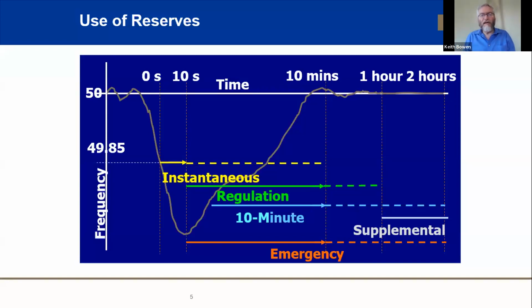We have an emergency capability, which is really the gas turbines, the diesel generators. They have the capability to run for an extended period of time, but they take between 20 to 30 minutes to start up. So they can't respond when there's an event on the system - they take a little bit of time to pick up. So you use your other reserves, bring up the gas turbines, and then try to restore the other reserves so it's there for the second event.